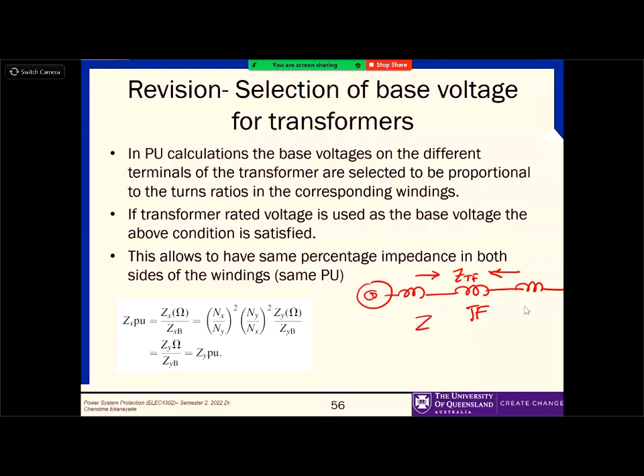If I am looking at ZTF from the low voltage side, it should be equal to ZTF from the high voltage side, in per unit. From both sides, it has to be the same impedance. You can only get that if you stick to the criteria where the base value from the primary side and the base value from the secondary side are equal to those winding terminal ratios. So, let's say this side is 11 kV and the other side is 132 kV, you can get the same impedance only by selecting those voltages like that. That's why when you are jumping across transformers, you have to select it in that specific way.